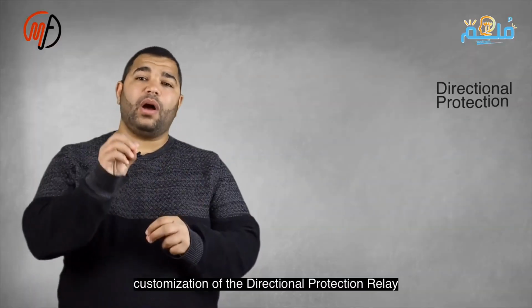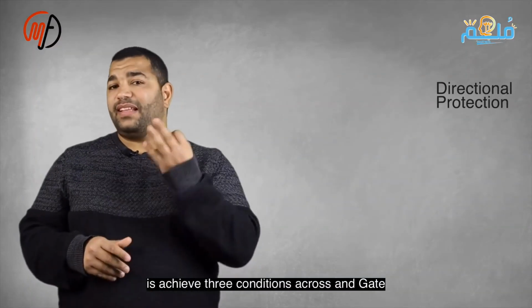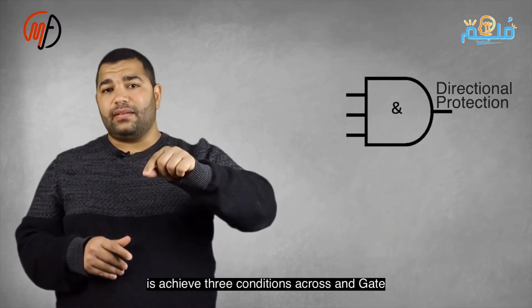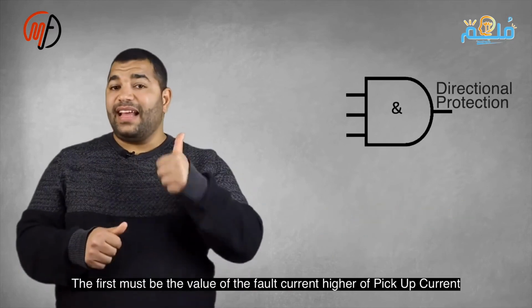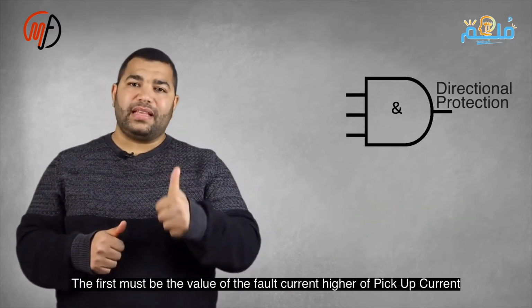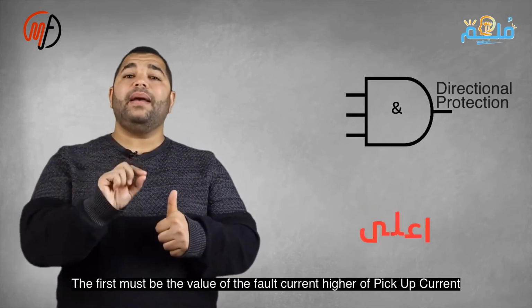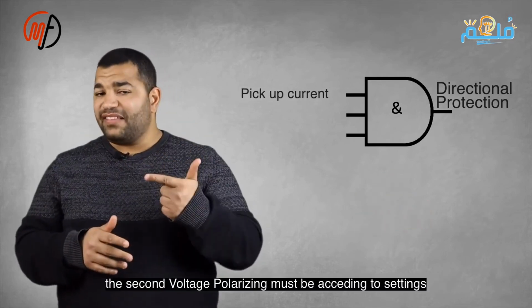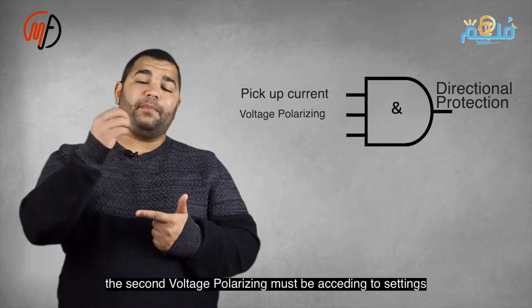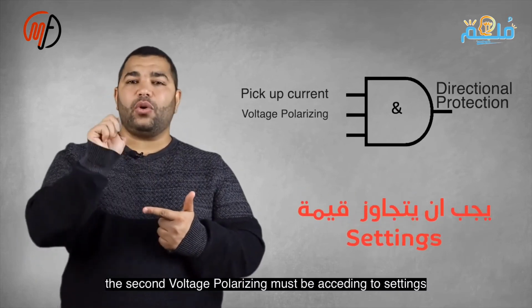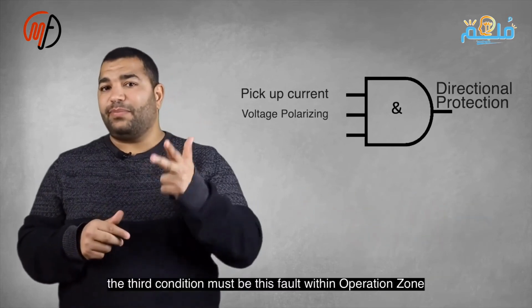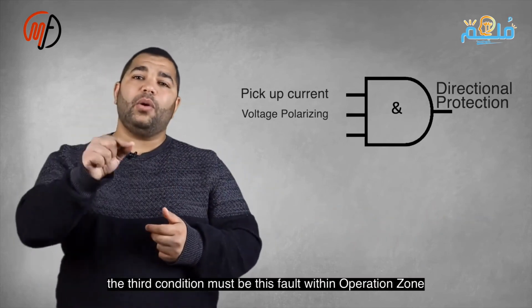The summary of operating the directional protection relay can be condensed into 3 points. They must all be met together as an AND gate. The first point is that the fault current value must be higher than the pickup current value. The second point is that the voltage value must exceed a certain threshold. The third condition is that the fault should be within the operating zone.